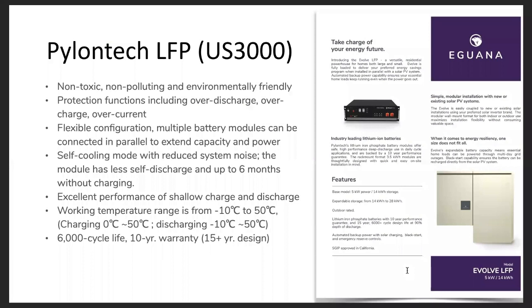A quick look at some of the features of the PylonTech LFP battery module. The LFP chemistry basically is considered to be non-toxic, non-polluting, and more environmentally friendly than the NMC chemistry. The protection functions included are over discharge, overcharge, overcurrent, kind of basic stuff. It does have a flexible configuration where multiple battery modules can be connected in parallel to extend the capacity and power.